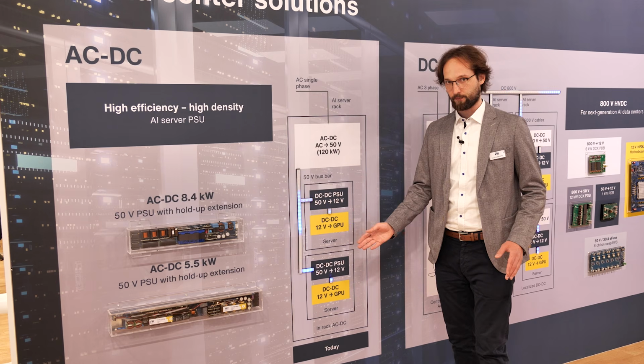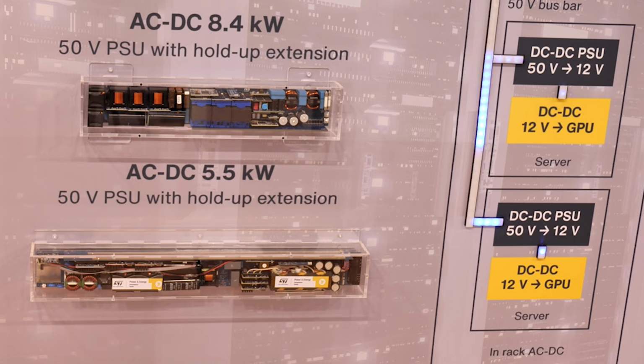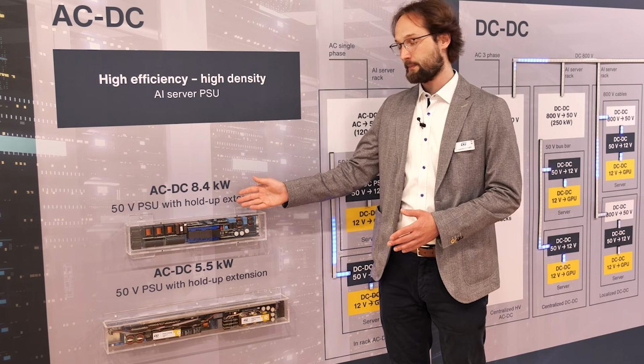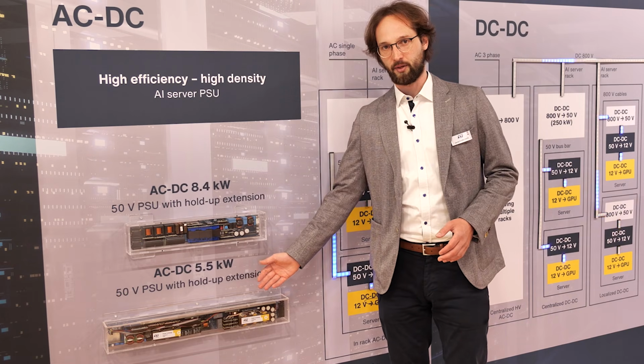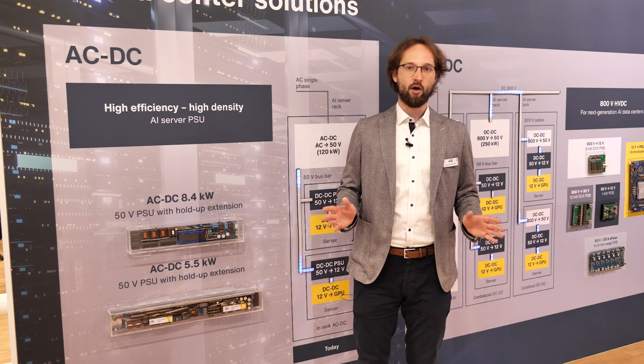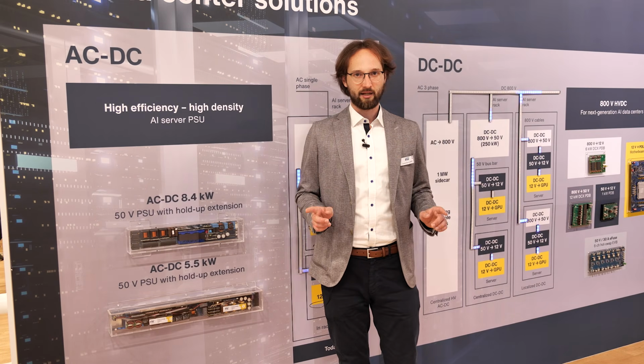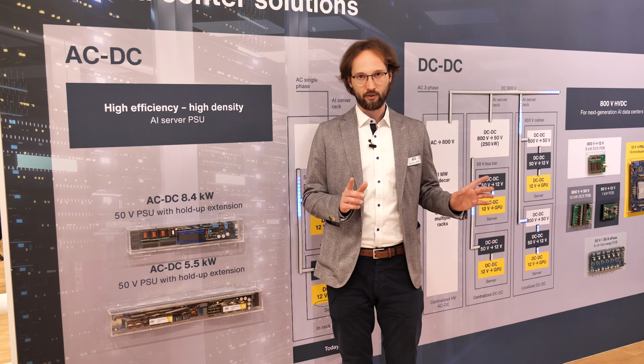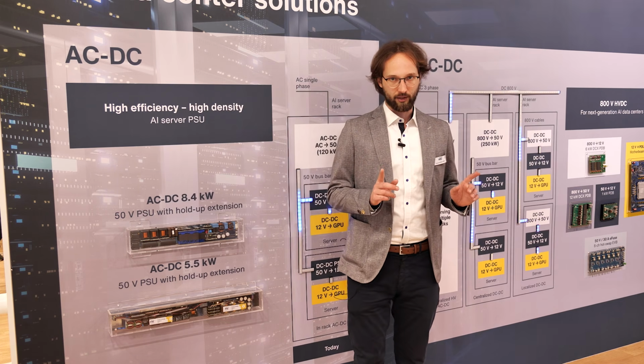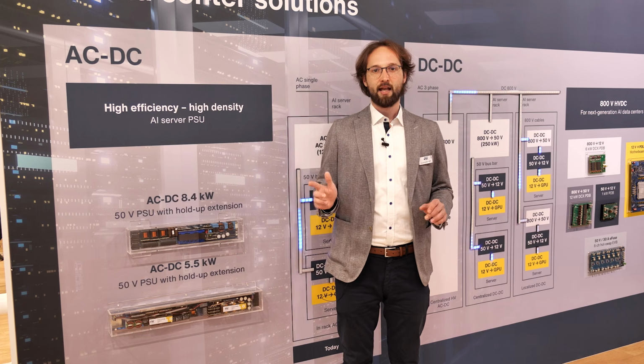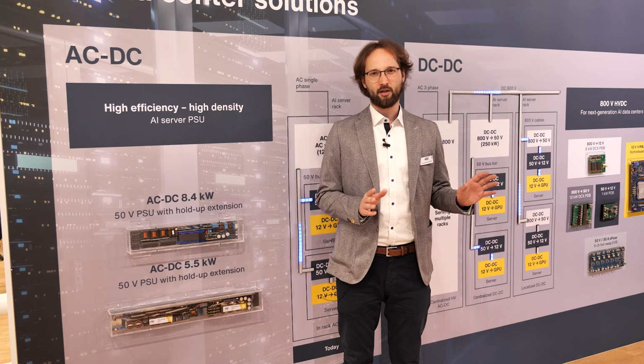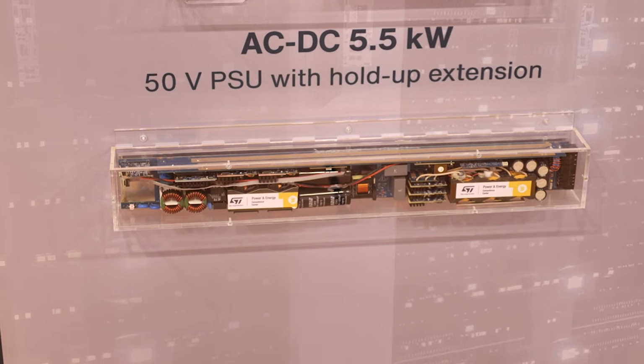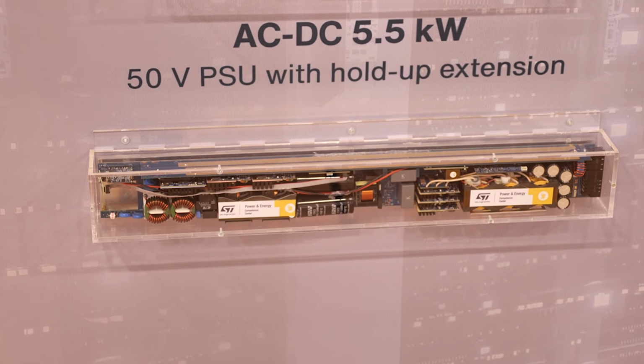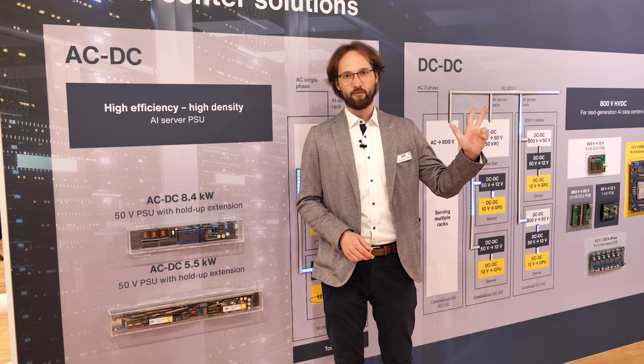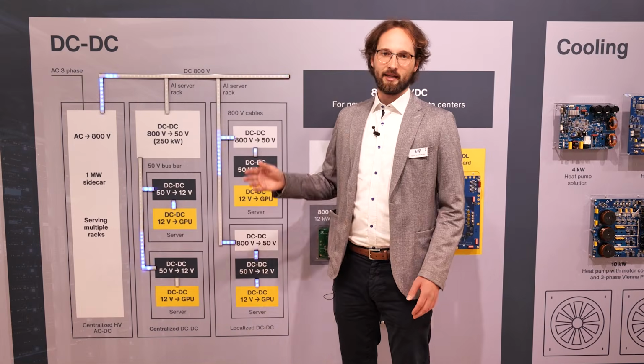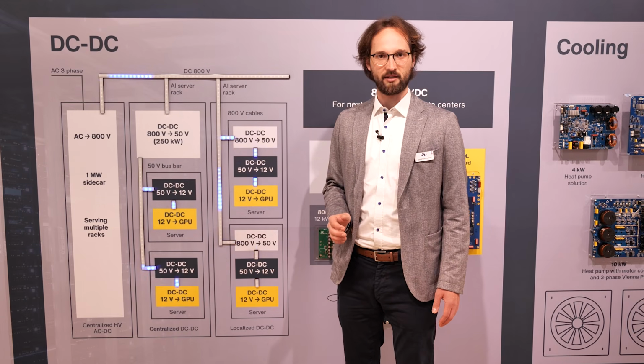ST offers two reference designs for the rack front-end power supplies, an 8.4 kilowatt unit and a 5.5 kilowatt unit. Both include a hold-up extension capability, so the rack runs through grid disturbances without dropping the load. This architecture is high efficiency, very high power density, and it is possible due to the optimal combination of specific technologies: silicon carbide input stage, backed with gallium nitride for the hold-up extension, and silicon for the secondary stage and the logic.